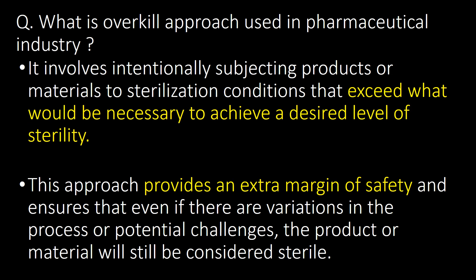What is the overkill approach used in the pharmaceutical industry? It involves intentionally subjecting products or materials to sterilization conditions that exceed what would be necessary to achieve a desired level of sterility. This approach provides an extra margin of safety and ensures that even if there are variations in the process or potential challenges, the product or material will still be considered sterile.